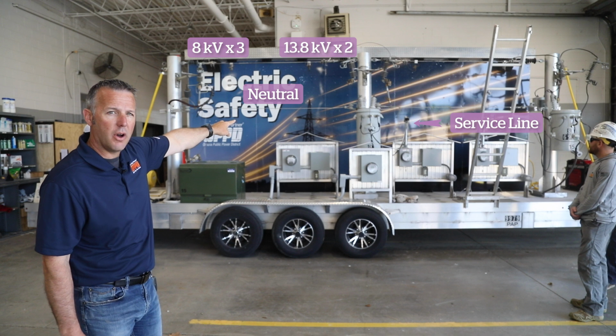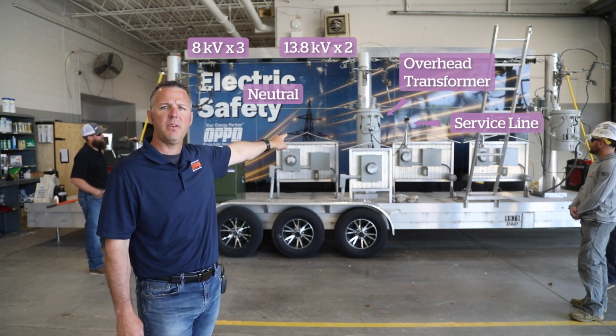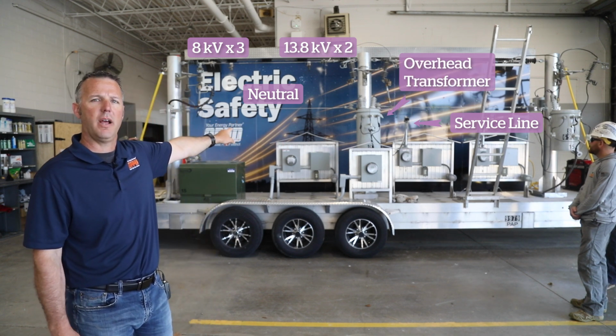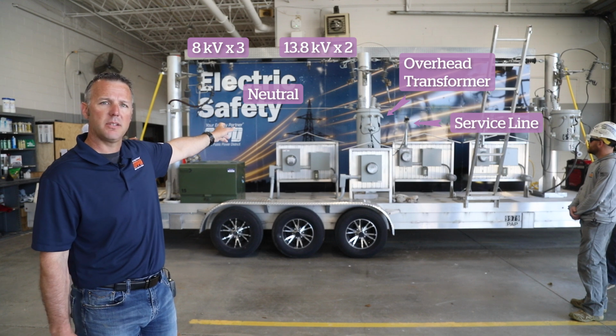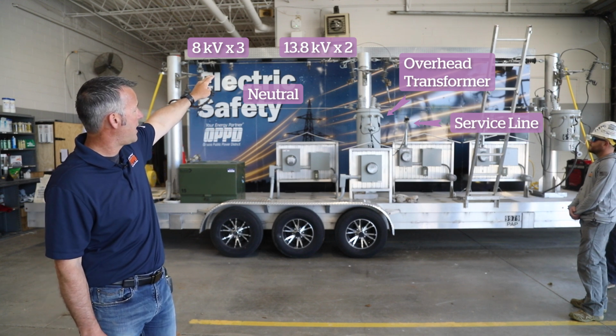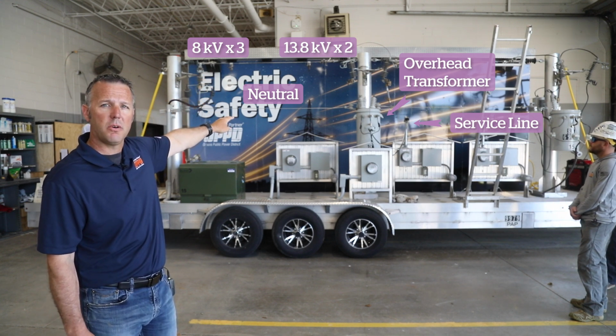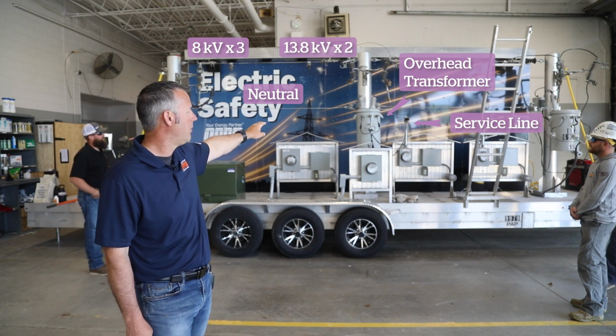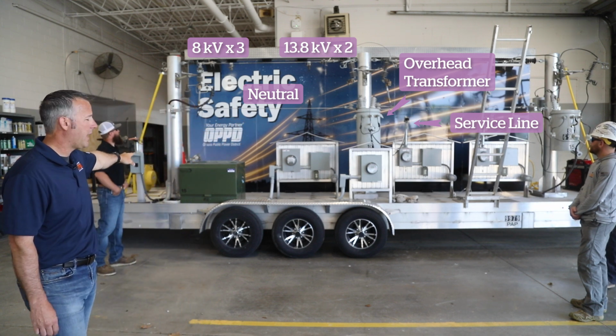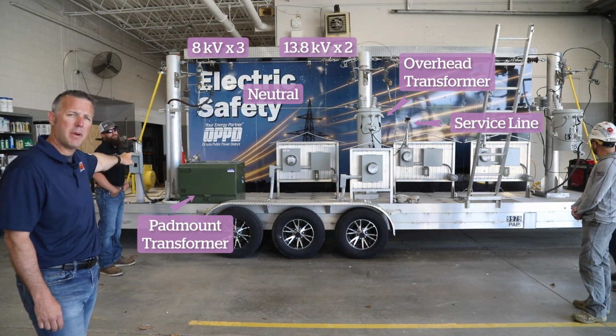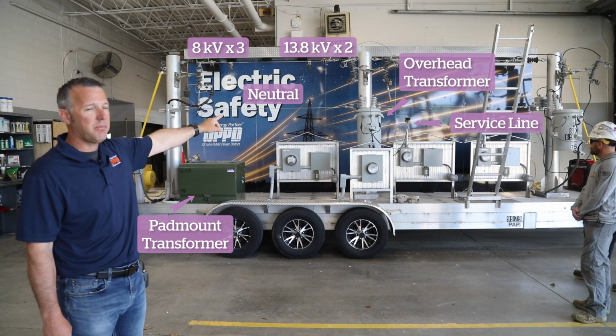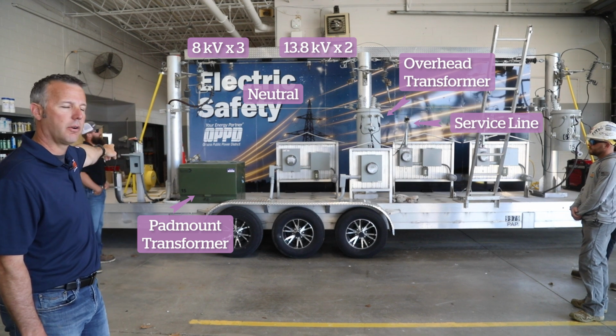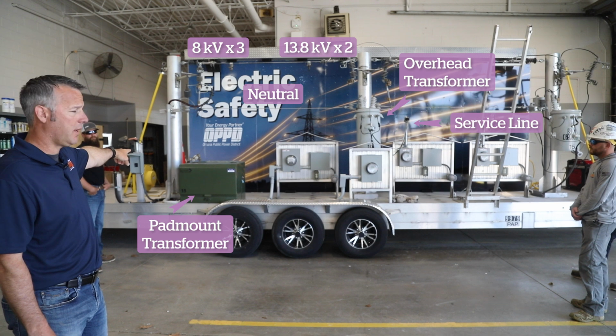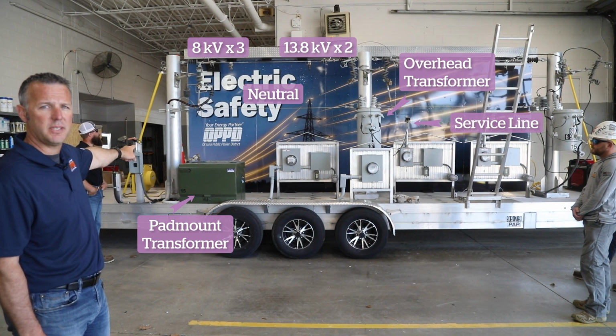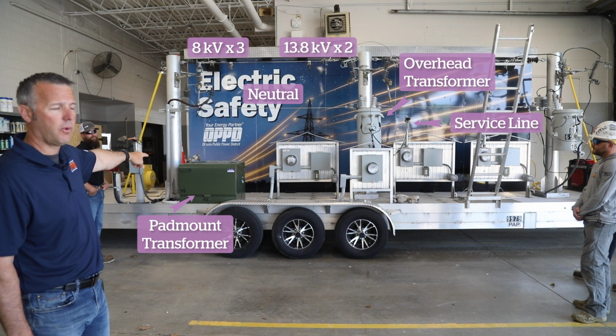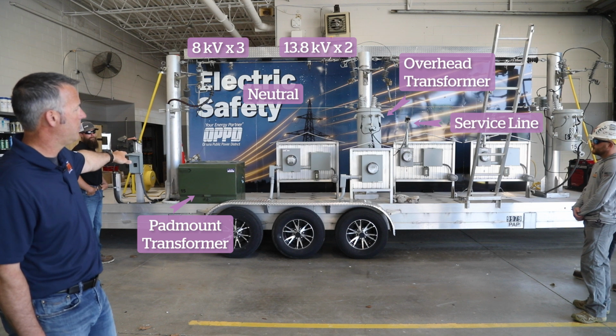The lower part is an overhead transformer. That's something you'll see in backyards in your neighborhoods in an overhead area. It steps down the 8,000 from the top to a usable voltage, 120/208. If you're in a neighborhood that has a pad mount transformer, it's the same thing as the overhead one, but underground. It takes 8,000, steps it down to 120/240, and that also powers your house.